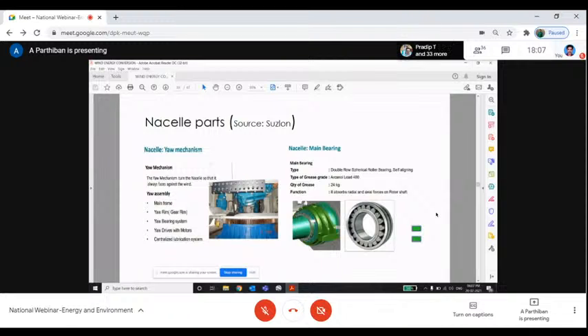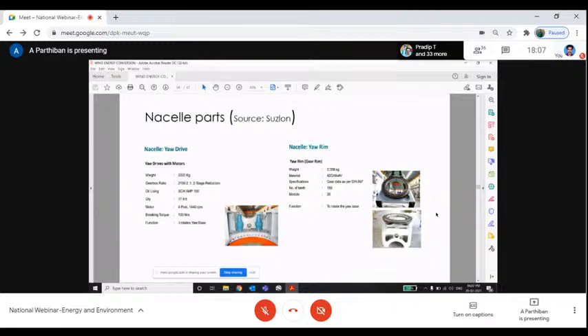Further, I will show the yaw drive and all. So this is the yaw drive. In each WTG there will be a minimum of 3, 4, or 5, based on the capacity. Some WTGs will have 4 yaw motors, some will have 5 yaw drives, based on the weight of the nacelle. For example, the total tonnage of the tower section is around 150 to 200 metric ton, and the nacelle, as a massive component, is around 60 to 80 metric ton in the commercial market. And the hub will have a total of three blades, and the hub will have around 25 metric ton.